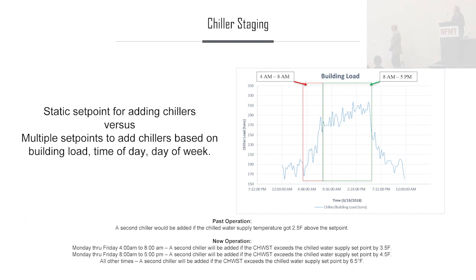All right, and this next example, again at AdTran, had to do with the chiller staging. The existing operation, that's an eye chart for everybody here, but it was just the standard sort of, hey, bring the second chiller on once supply temperature gets 2.5 degrees above set point, bring on the next chiller.